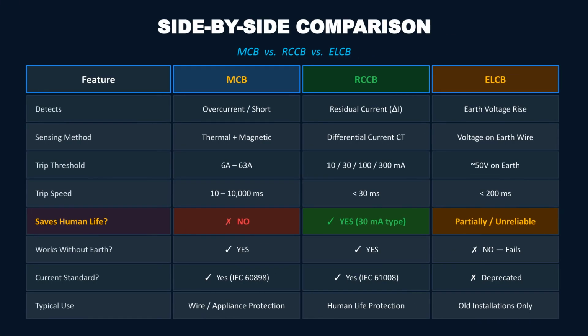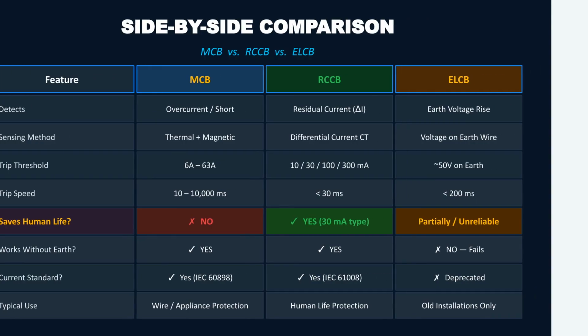In this side-by-side comparison, the RCCB stands out. It detects small residual currents and trips in less than 30 milliseconds, reliably saving human life. The MCB does not save lives, and the ELCB is unreliable due to its dependency on a perfect earth connection.